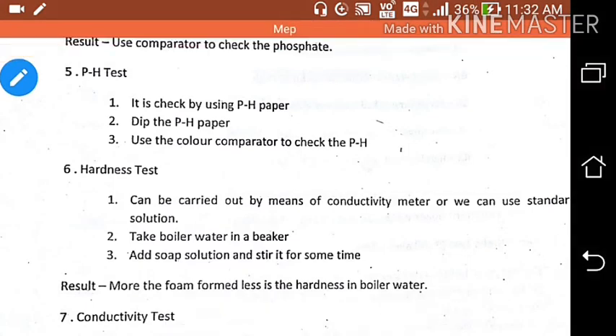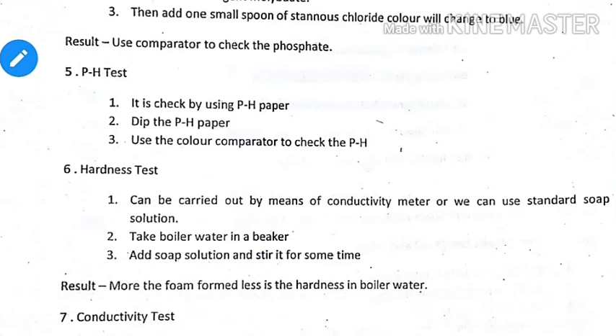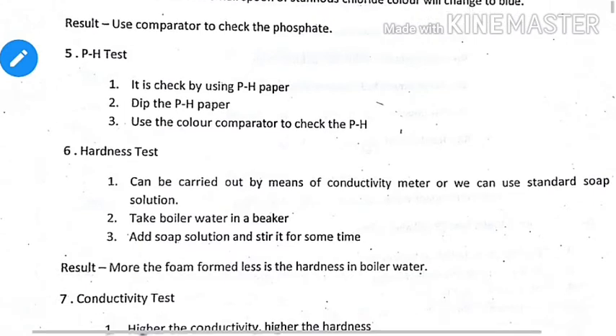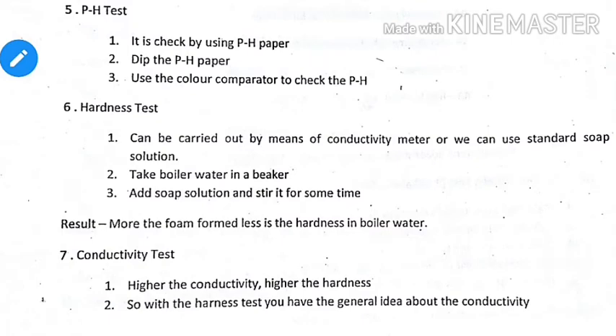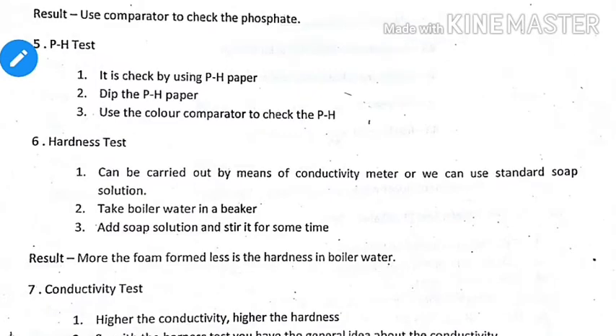The hardness test is done to check for salts causing hardness in the boiler water. Hardness can be due to calcium carbonate, so we determine its concentration. Hardness can be checked using a conductivity meter, or by using a standard soap solution: take boiler water in a beaker, add soap solution and stir. More foam formed means less hardness of the boiler water.